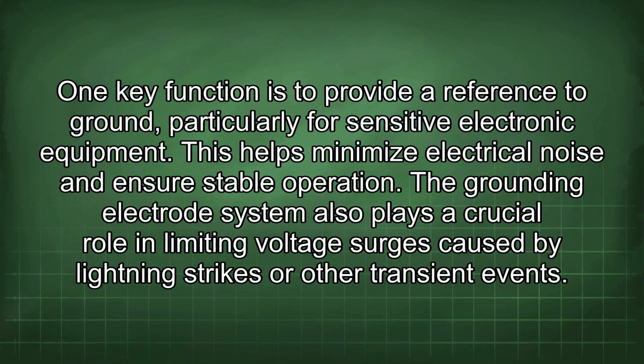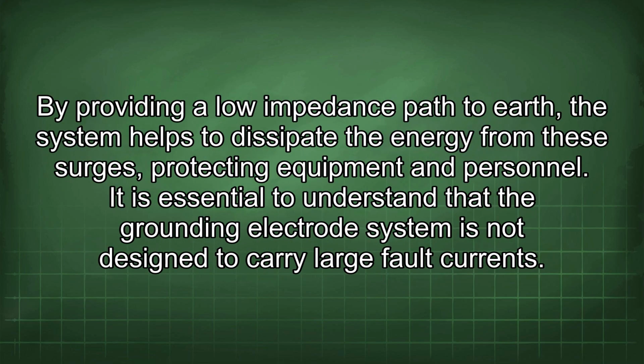One key function is to provide a reference to ground, particularly for sensitive electronic equipment. This helps minimize electrical noise and ensure stable operation. The grounding electrode system also plays a crucial role in limiting voltage surges caused by lightning strikes or other transient events. By providing a low impedance path to earth, the system helps to dissipate the energy from these surges, protecting equipment and personnel.